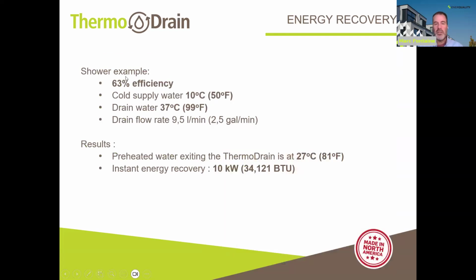If we have a higher efficiency unit, then we can look at the 10 degrees going up to 27 degrees. So that's a 17 degree Celsius increase in temperature. So it's quite significant. Heat recovery rates instantly, as you look at it, are usually in the 8 up to 10 kilowatts of instant power. So imagine you're reintroducing into the hot water heating system 8 to 10 kilowatts of heat load as you're utilizing the thermodrain.